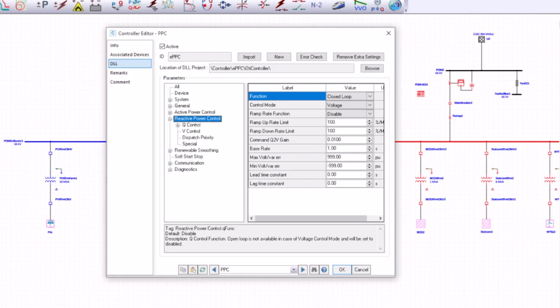Next, we have reactive power control, which is similar to active power control in the sense that it uses a PI controller to regulate the power at the point of interconnection. It regulates one of three variables at a time: the reactive power, power factor, or voltage. It also supports a droop-based QV scheme adjusting reactive power during voltage fluctuations, and it has a ramp rate limiter to limit the rate of change of reactive power at the point of interconnection.